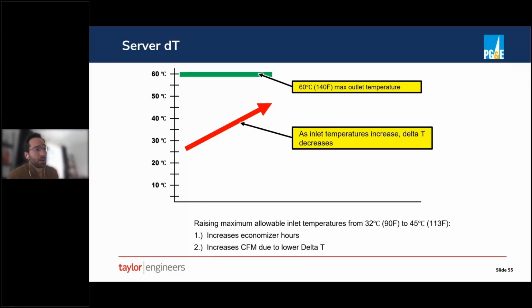It's essentially about the higher the entering air temperature that we design for, often that means the lower delta T and therefore bigger air handling. One important thing to note is that from an efficiency perspective, there can be a significant benefit there. If we have an airside economizer, for instance, the higher we allow the entering temperature to be, the more economizer hours that we'll get out of the system.